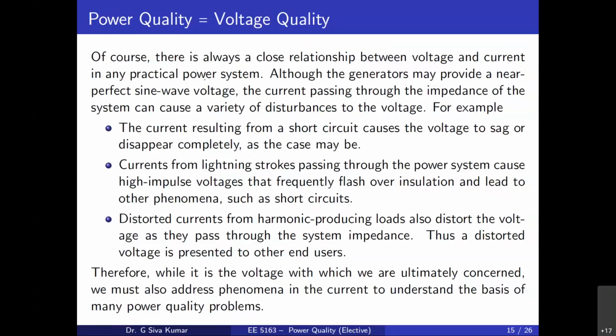This is the feeder impedance ZS, and this is VT, which equals VS minus (IL plus IF) times ZS. This is the equation for the terminal voltage that we have been measuring. Keeping this figure in mind, you can see that the current resulting from a short circuit causes the voltage to sag or disappear completely, as the case may be.